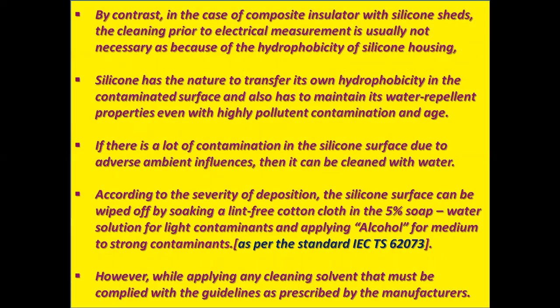By contrast, in the case of composite insulators with silicone sheds, cleaning prior to electrical measurement is usually not necessary because of the hydrophobicity of the silicone housing. Silicone is such a material whose hydrophobicity is much higher. Silicone has the nature to transfer its own hydrophobicity to the contaminated surface and also to maintain its water repellent properties even with highly polluted contamination and age.